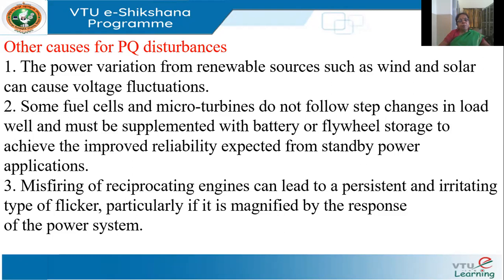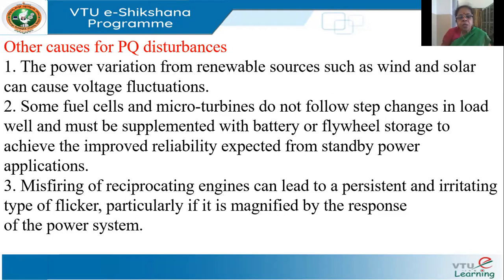The third problem which can arise is misfiring of reciprocating engines. Engines coupled to a generator are also used as distributed generators. When the engine doesn't fire properly, you can have a very irritating flicker, which can be magnified depending on the configuration of the power system at the point of interconnection. These are some of the issues we are likely to have with distributed generation.